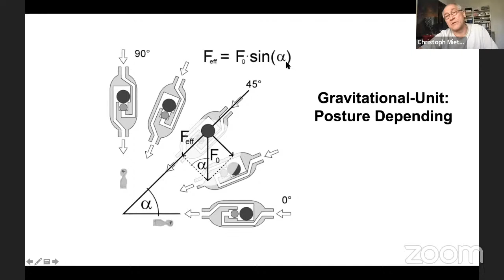And with this angle, it's becoming higher up to maximum, and you can calculate the opening pressure with this equation. So here, once again, at an angle of 45 degrees, this device has already 0.7 multiplied with maximum opening pressure as a compensation, depending on the posture of the device. So what does it mean in the shunted patient? Here we have again the model. This is the DP valve, which is establishing this difference to the abdominal cavity, let's say from here to there.